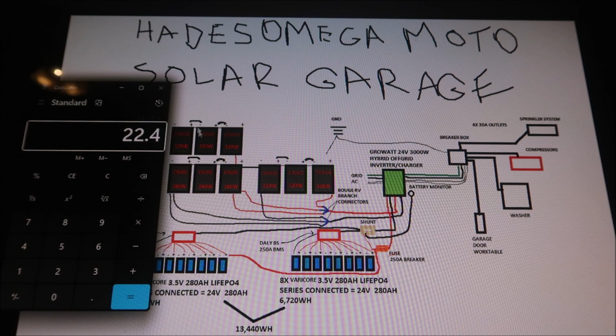That may be wrong, I'm not sure, but anyway you get about 24 volts, guys, because it's a 24 volt system. The inverter is 24 volts. So that's 24 volts times 280 amp hours, and that gives us 6.72 kilowatt hours, or 6,720 watt hours.